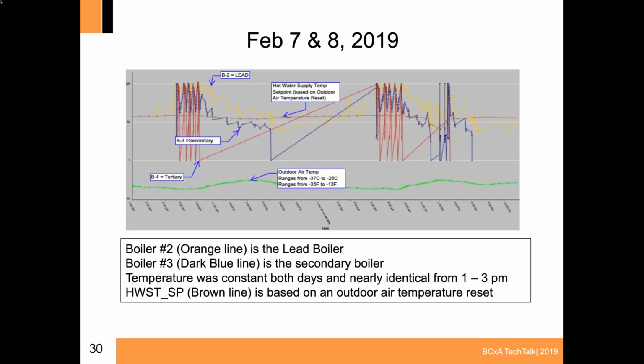So on the next 4 slides, I'm actually going to show you what the trends looked like and what we were looking at. So on the left-hand side of the screen is February 7th, and then on the right-hand is February 8th. And on February 8th, between about 1 and 3 p.m., you can actually see the brown line, which is the hot water supply temperature set point, where we manually adjusted that to see if it could handle it. The orangish colored line is the primary lead boiler, boiler 2, and boiler 3 is the secondary one.